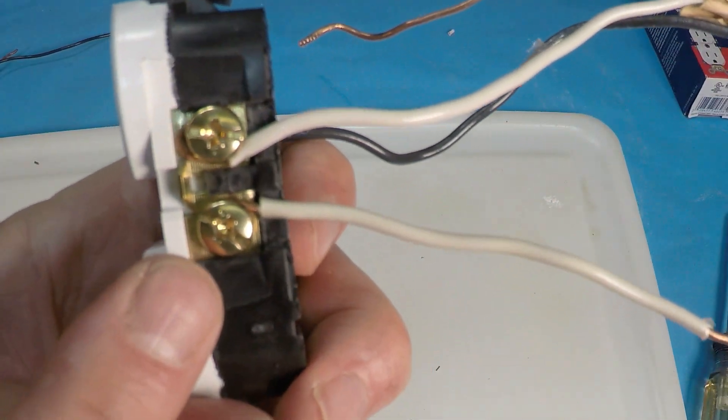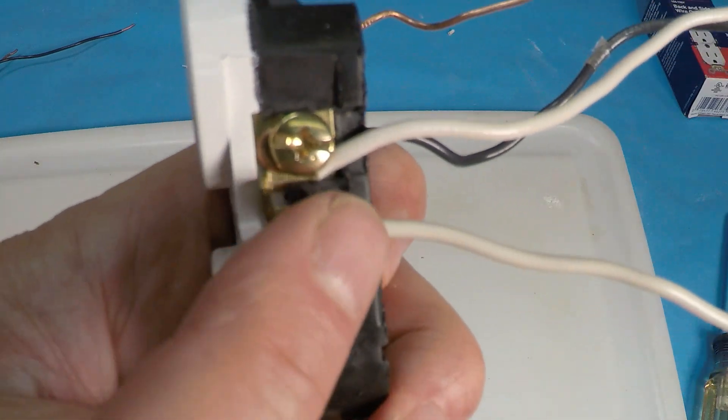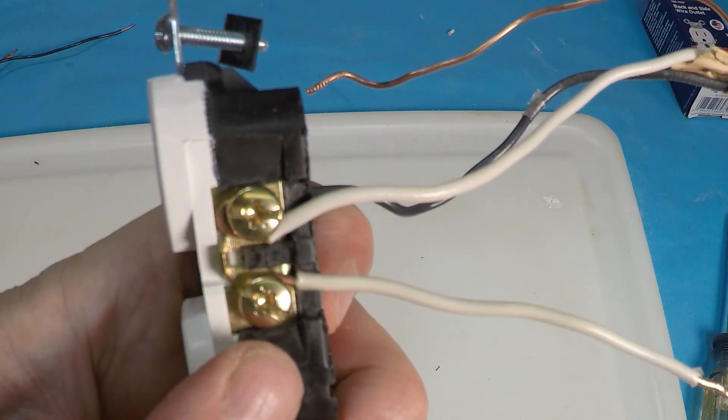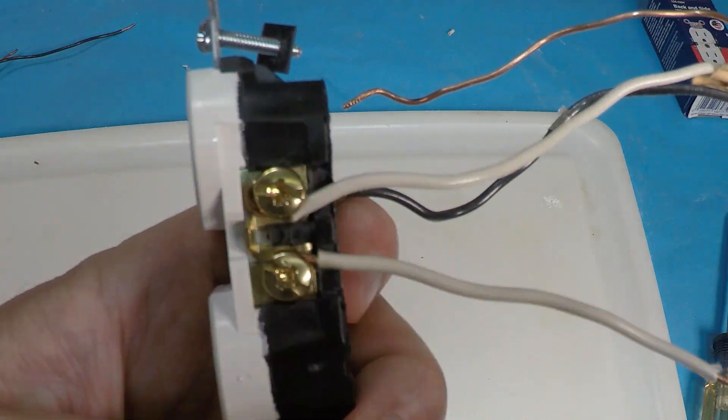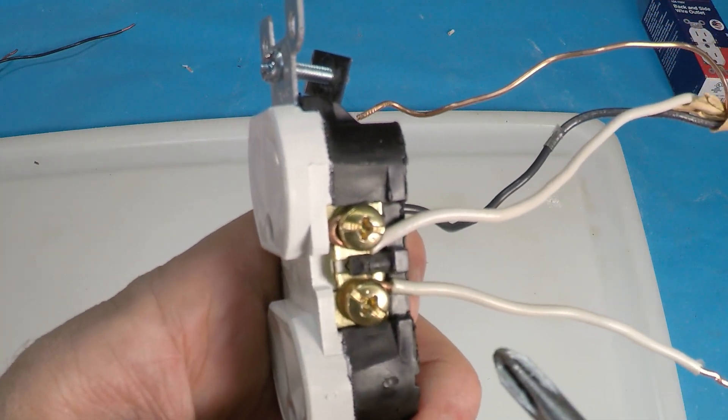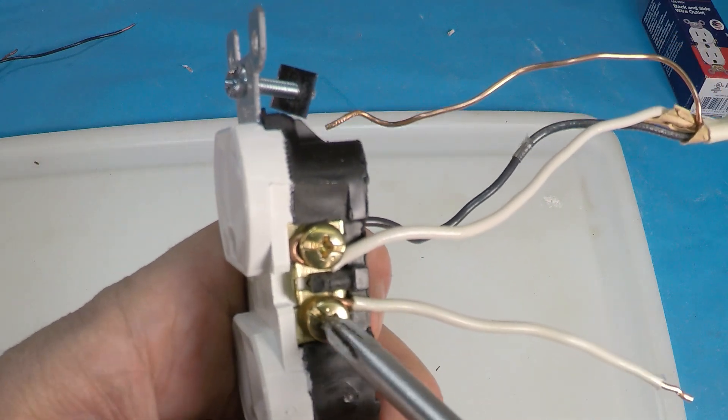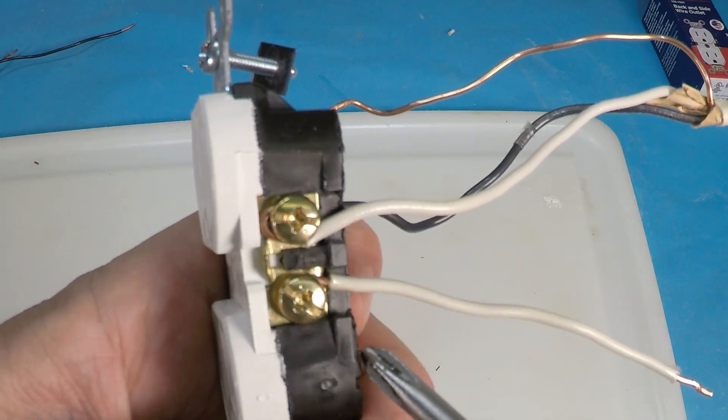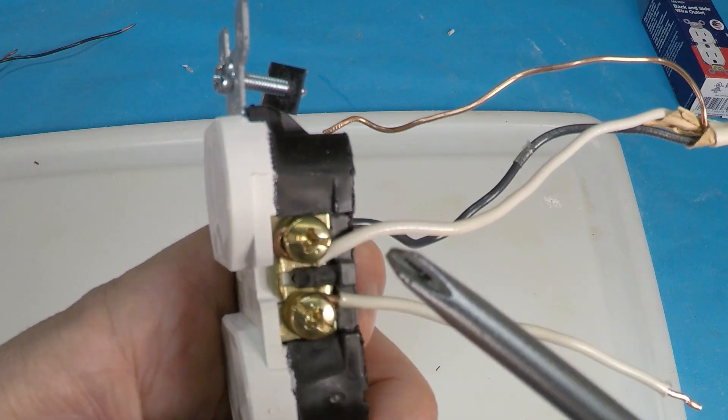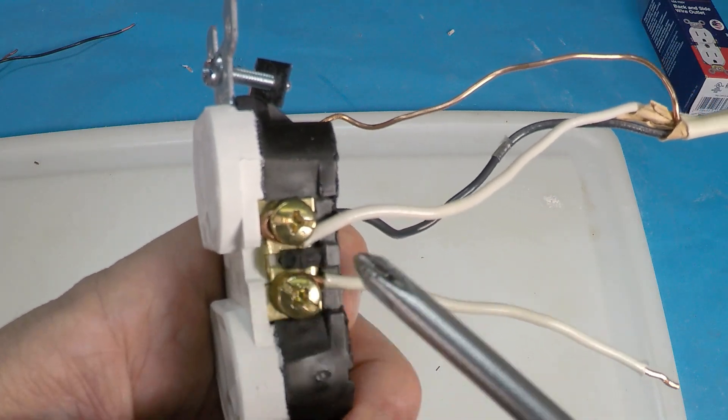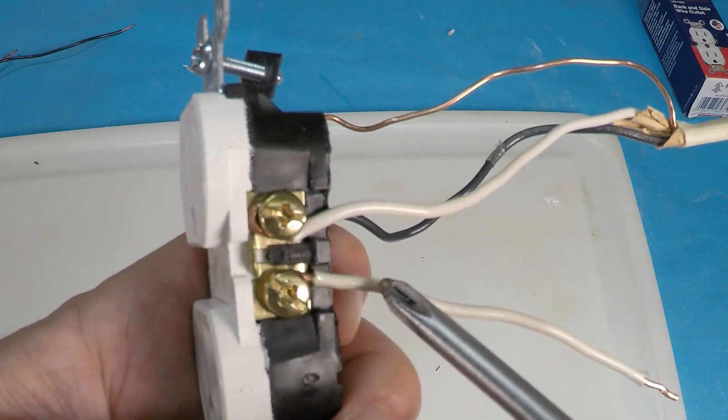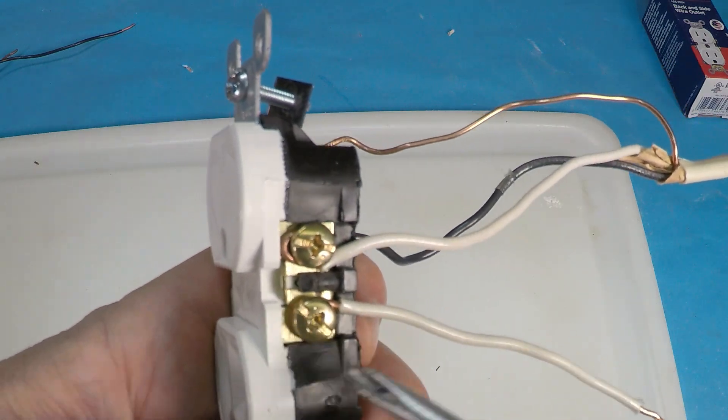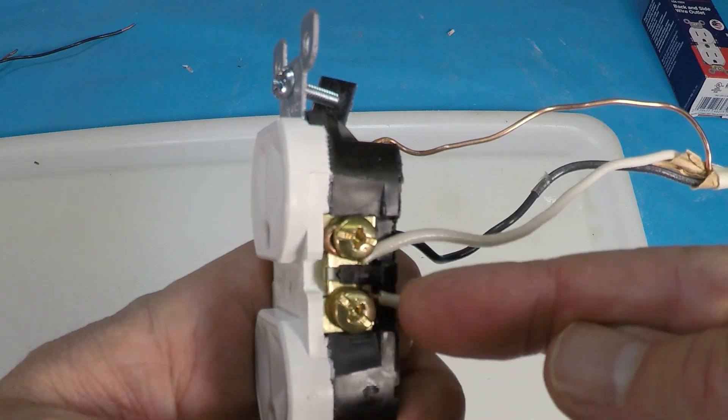Since I have this one here, you could see that this J hook is wrapped the wrong way. It's going counterclockwise, it's supposed to go clockwise. As you tighten down on it when it's the wrong way, it's going to push the wire back out. It's going to loosen it, unless you're really holding it in with your other hand.